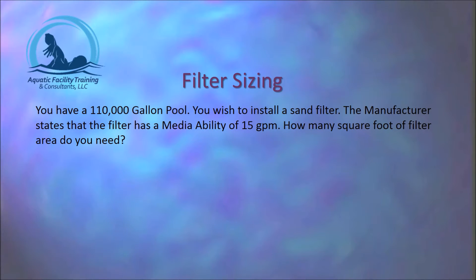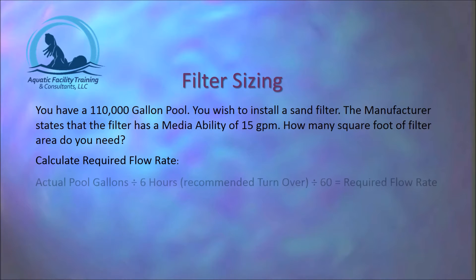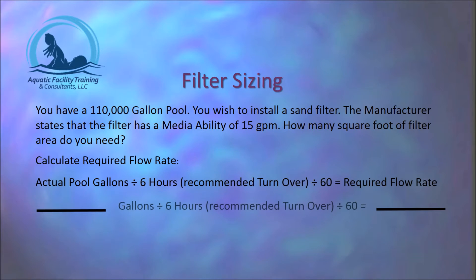In this example, we have a 110,000-gallon pool and we wish to install a sand filter. The manufacturer states that the filter has a media ability of 15 gallons per minute per square foot. First, we calculate the required flow rate: actual gallons divided by 6 (our recommended turnover rate) divided by 60 gives us our flow rate in gallons per minute. 110,000 gallons divided by 6 divided by 60 equals 305.5 gallons per minute.